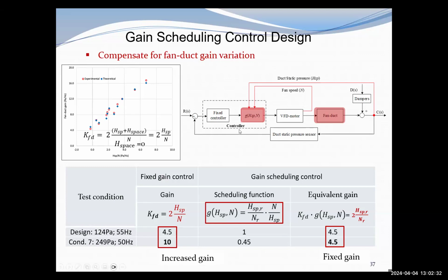Okay, thank you, Renee. I was just wondering, do you think this will be a standard control procedure that gets shipped on physical units in the near future? Yes, actually, we tend to reset the duct static pressure on lower load conditions. That will be good because if we reduce the duct static pressure on the lower load condition, it will reduce this fan duct gain. I just meant, do you think Trane or Johnson Controls or somebody is going to start implementing this soon? Because it seems like really good results. Yes, I do think this controller is very simple, it's generic, and very easy to implement.